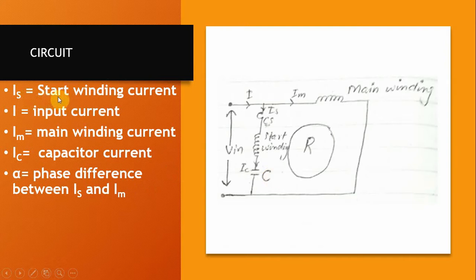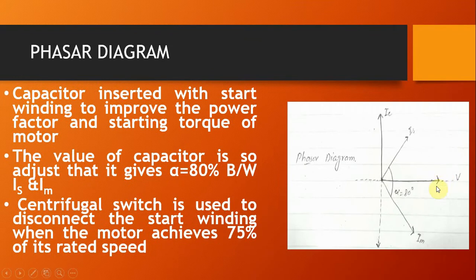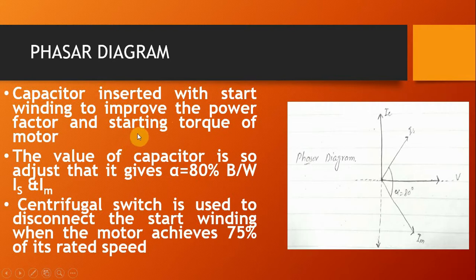IS is the starter winding current, I is the input current, and IC is the capacitor current. Alpha is the phase difference between IS and IM. As you can see in the phasor diagram of the capacitor start motor, the alpha between IS and IM is 80 degrees. The capacitor is inserted with the starter winding to improve the power factor and increase the starting torque of the motor. The capacitor value is adjusted so that the phase difference alpha between IS and IM is 80 degrees.